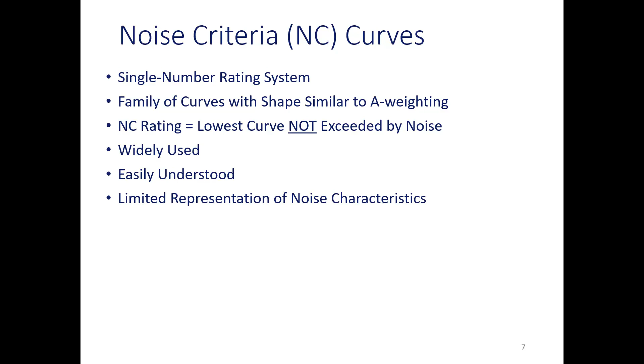There are some similarities. It's a single number rating system, but the difference is here we have a qualitative indicator. So the part about it being rumbly, hissy, tonal, or even rumbly and loud enough to produce noticeable vibration, we have all these characteristics that are applied to it. Neutral would be the good one. It basically follows the spectrum of human sensitivity, so no low end or high end or tone sticks out, which is usually more annoying. So you want neutral. Here an example, RC30N would be good for a school.